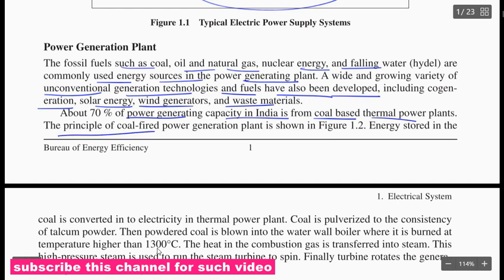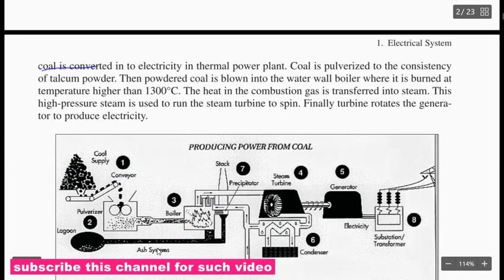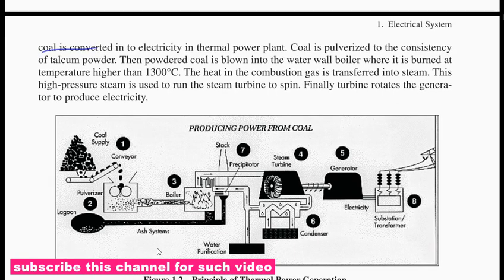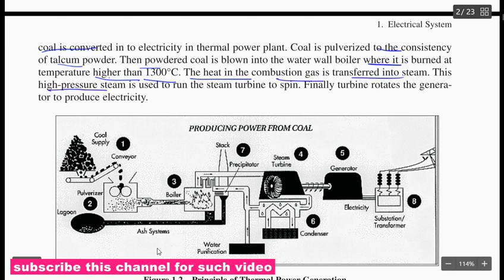The principle of coal-fired power generation plant is shown in the figure. Energy stored in the coal is converted to electricity in the thermal power plant. Coal is pulverized to consistency of talcum powder. The powdered coal is blown into the water wall boiler where it is burned at a temperature of higher than 1300 degrees Celsius. The heat in combustion gas is transferred into steam.